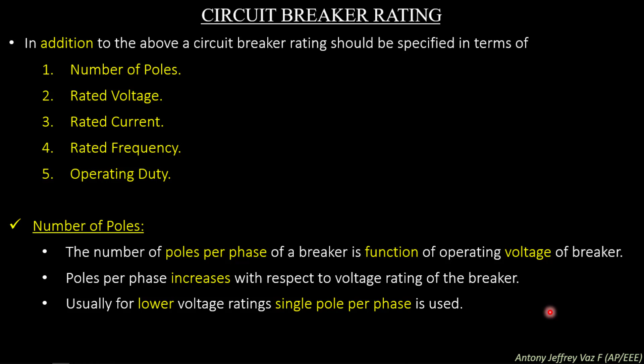Rated voltage. Under normal operating conditions, the voltage at any point of the power system is not constant. From a power system point of view, the operating voltage is not a constant. It will vary from area to area. So manufacturers guarantee perfect operation of the circuit breaker at maximum rated voltage, or rated maximum voltage. This rated maximum voltage must be higher than the rated normal voltage.